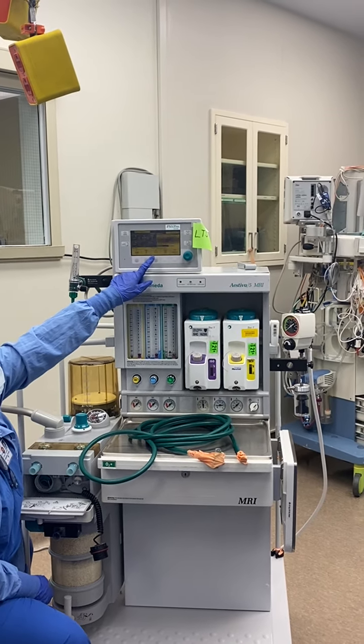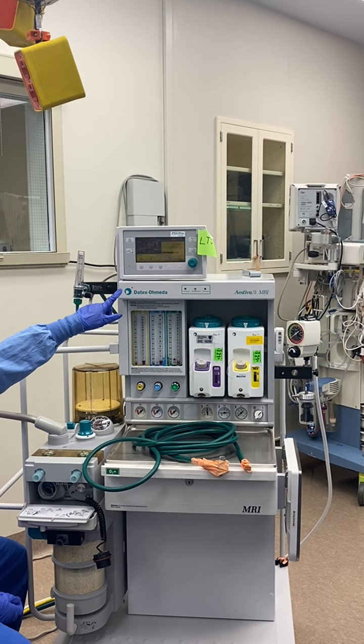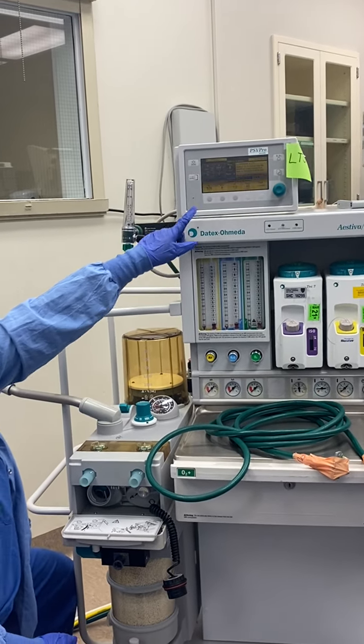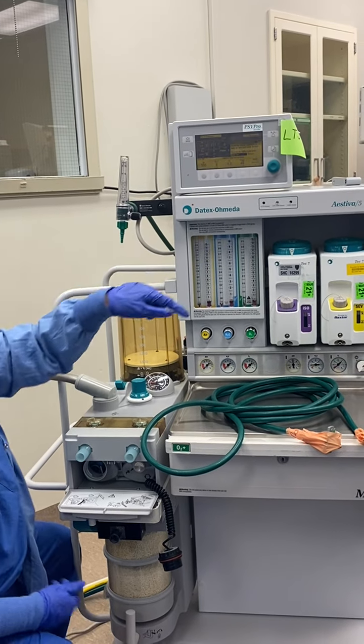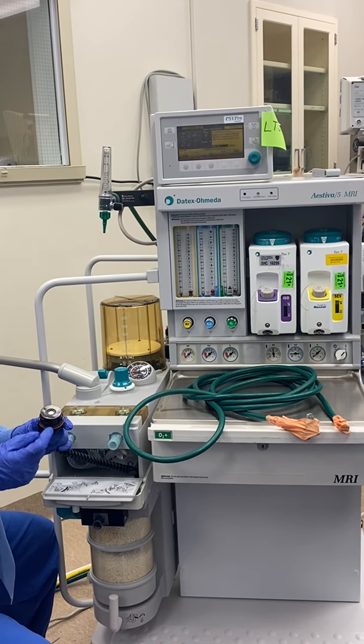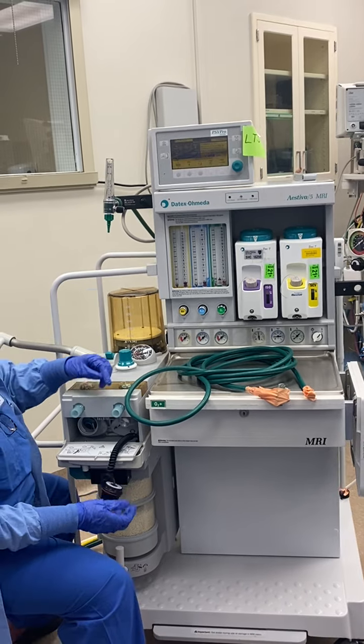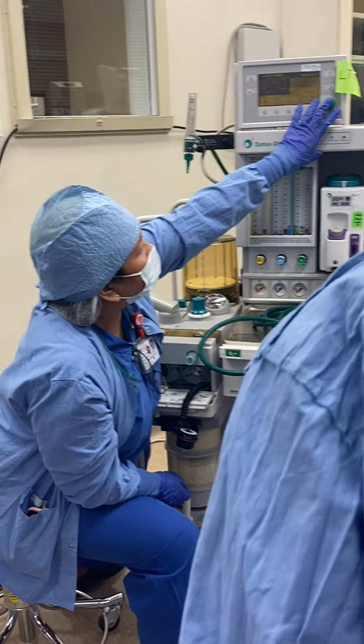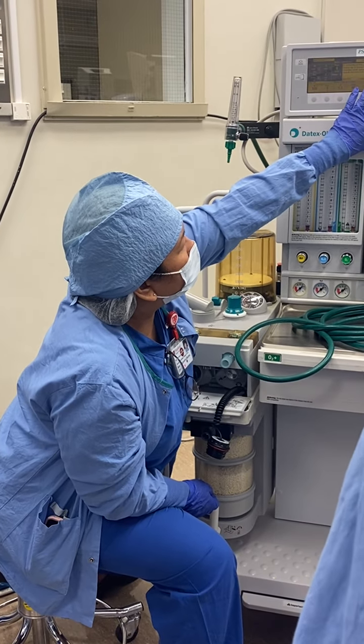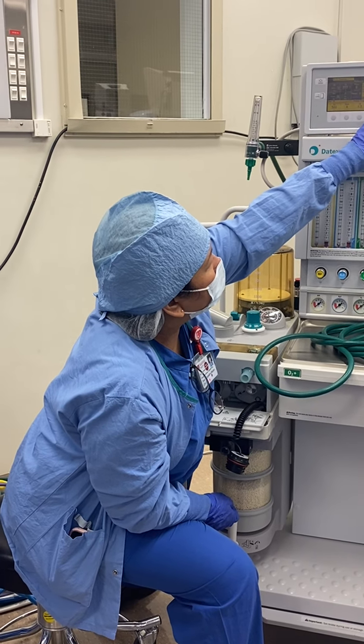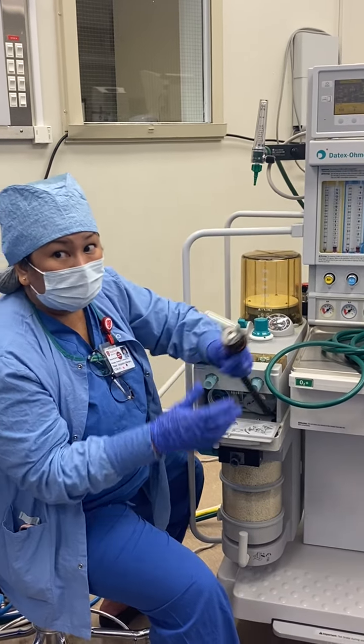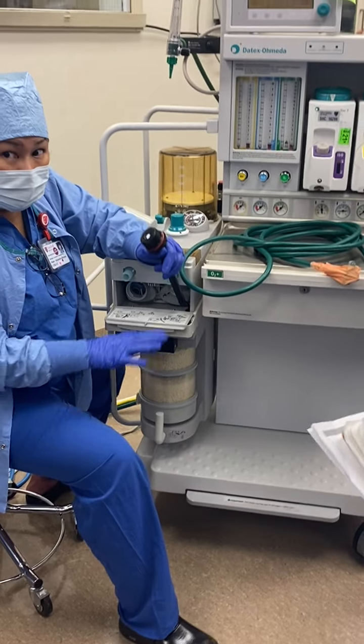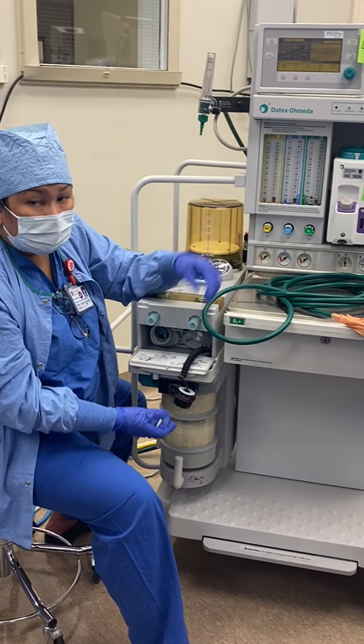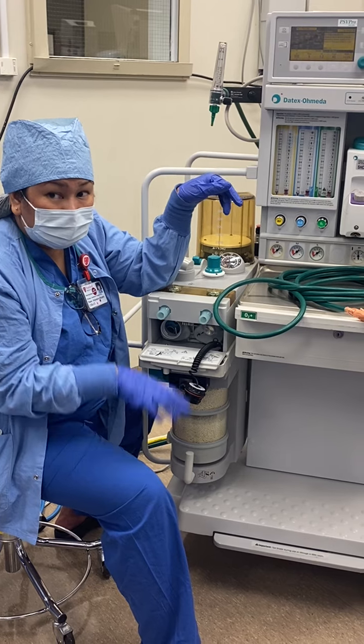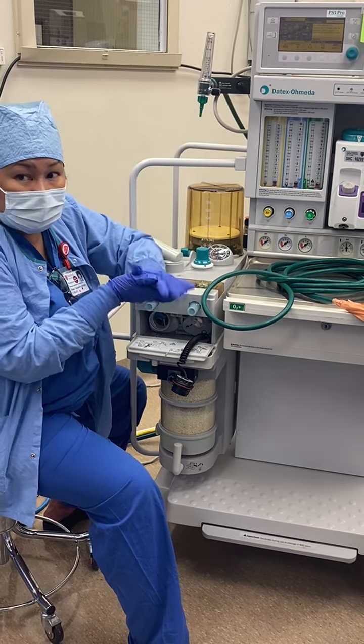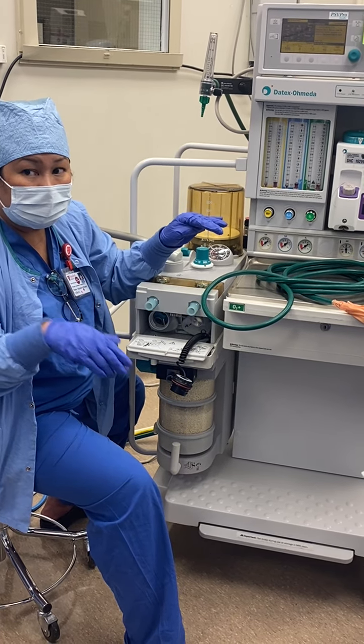Okay, retry or do 100%. So it failed. You see that? Yeah. Because it said replace O2, it wants me to replace this. So now it wants me to go to 100% calibration. So what's the difference between those two calibrations? Room air. It's getting a baseline for room air. And it's also getting the baseline for 100%. So when they're delivering 100%, the machine detects, okay, this is what 100% should be.